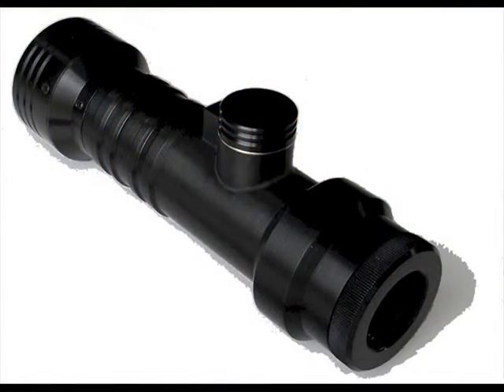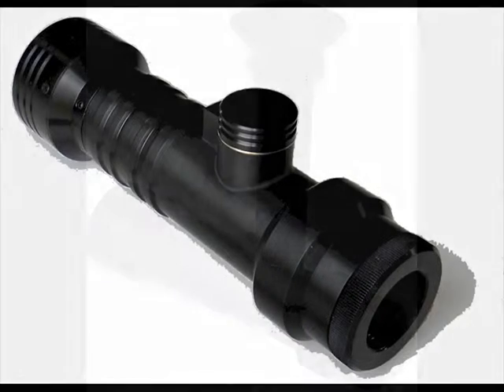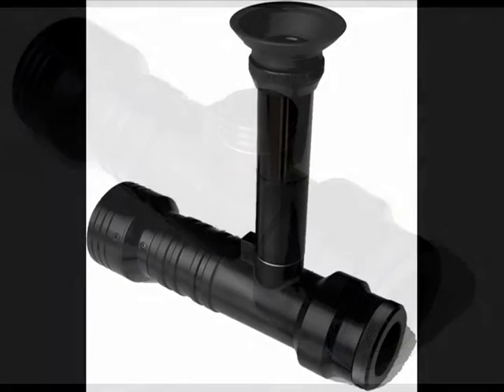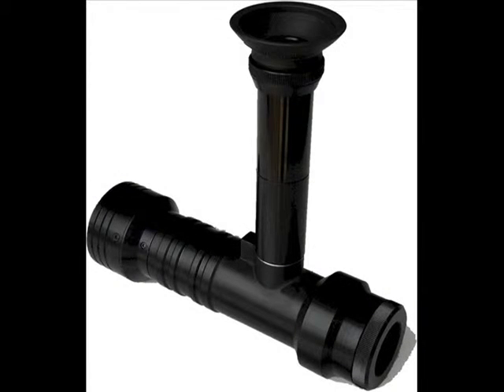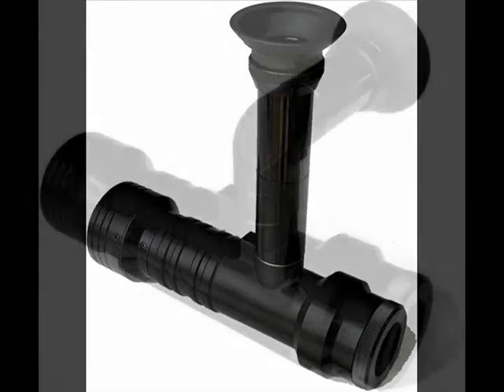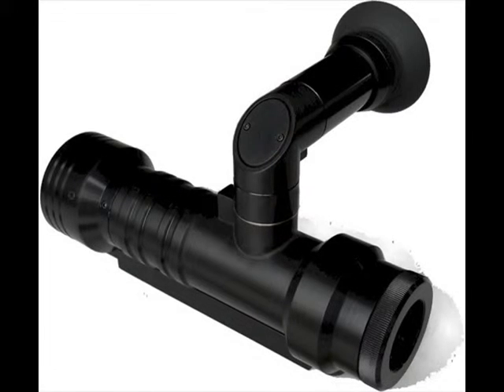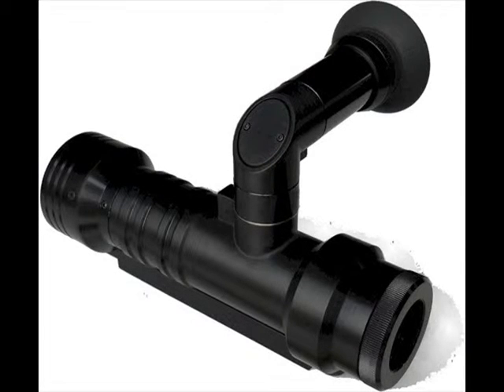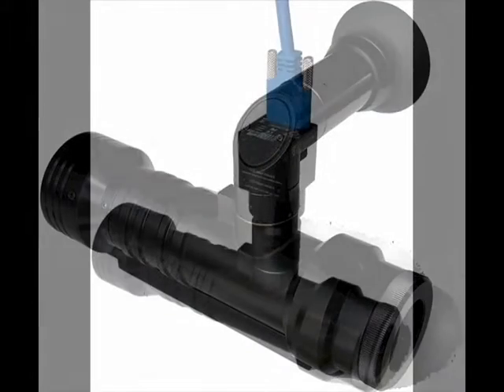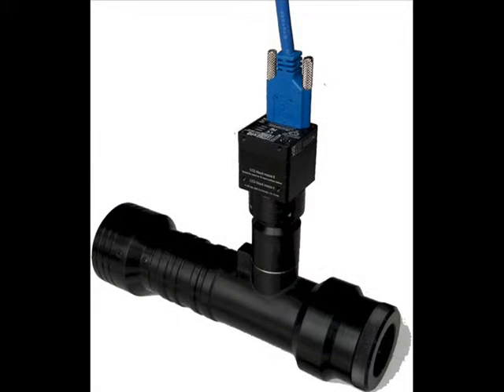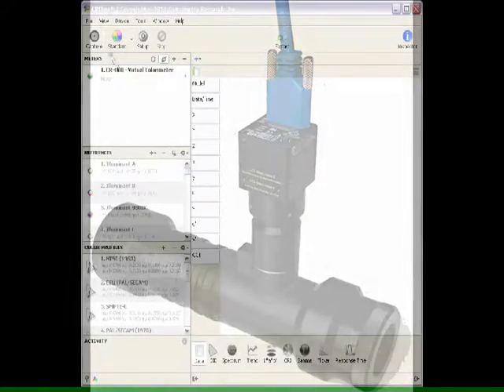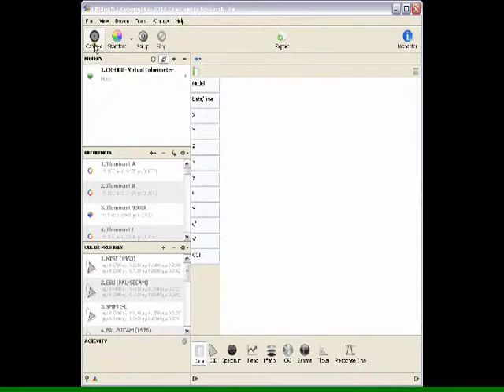The CR250 is a high resolution spectroradiometer in a very compact footprint with a 5 nanometer bandwidth and 1.6 nanometer per pixel resolution that excels in low light, highly accurate wavelength and color measurement. It's ideal for measuring current and future display technologies.